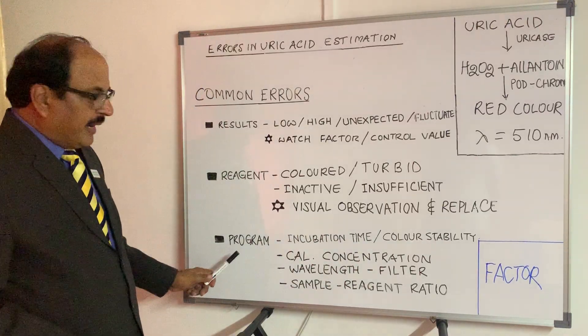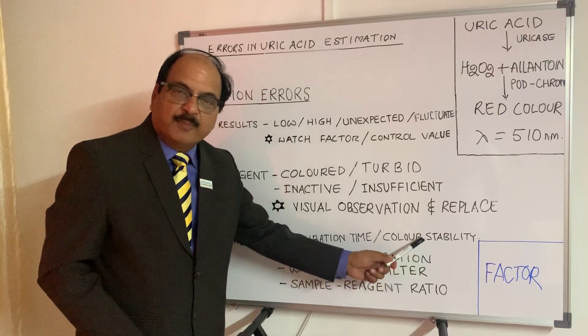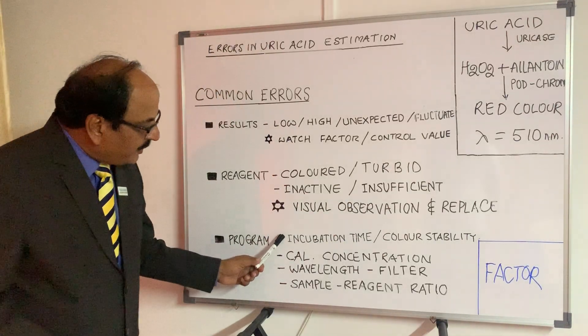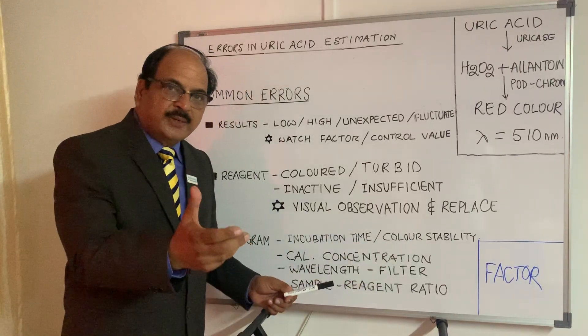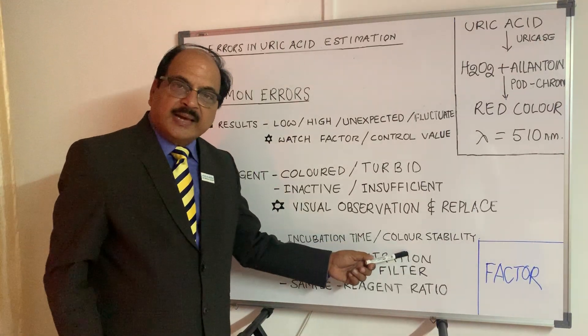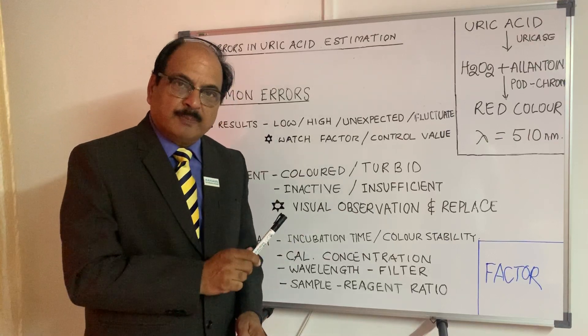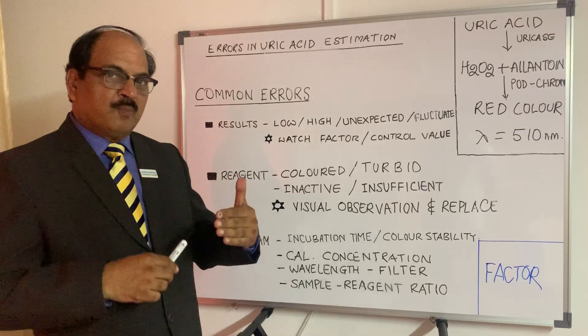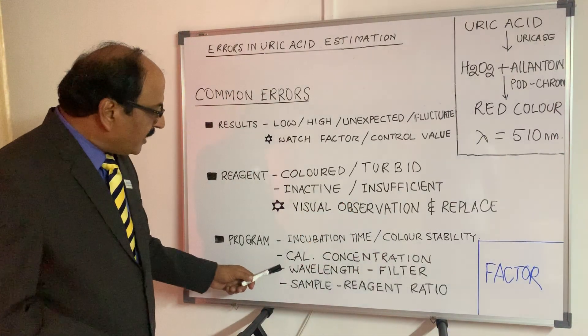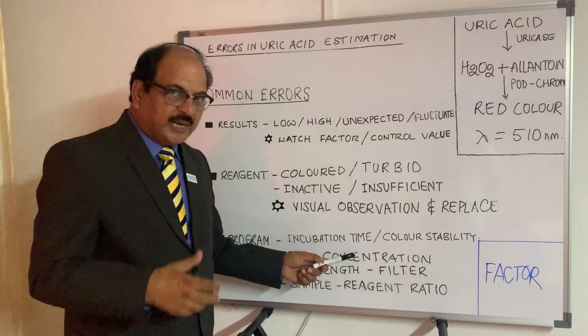Program-oriented errors: incubation time and incubation temperature are important, and color stability is also important. Every reagent manufacturer specifies the final color stability. So keep your incubation time, incubation temperature, and color stability monitored as per the manufacturer's technical insert. While calibrating your instrument, take care that the value of the lot of multi-cal used by you is entered into the program. This is important because multi-cal values are not fixed — they are manufactured by different people with different values. If you use the calibrator or standard concentration provided in the kit, this remains unchanged, but calibrator values can differ every time.